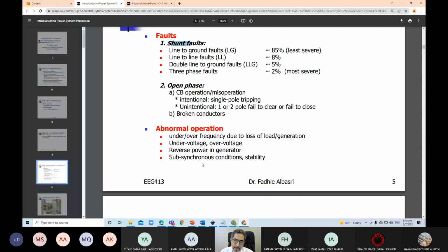It will drop below 50 if you are at 50 hertz. And that's why the governor will take action to correct it. The control systems that allow more steam for the steam turbine to generate more power try to correct this. But if it cannot correct this in a short time, then the protection system will take action to disconnect load, because you have more loads, so it will disconnect loads from the system to make a balance between load and generation power.